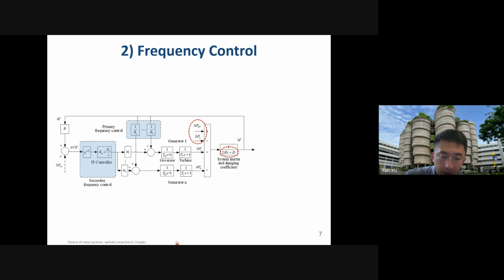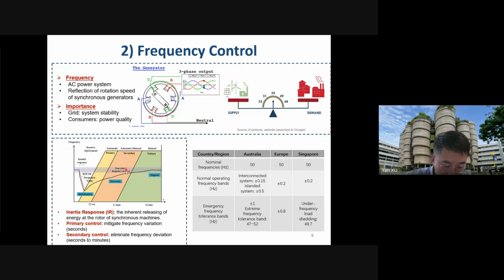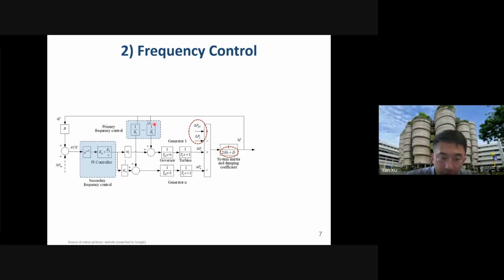Now, as I said, we have two control systems, primary control and secondary control. So you can see, given this delta F, this primary control block will immediately react to this delta F. Here you can see the control unit is 1 over R. R is the so-called regulation coefficient, or droop coefficient. Given this delta F and this R, each generator will have such a primary controller. Then it will generate a signal. This signal will change the position of the governor, and then it will allow more or less gas input, or energy input, so as to restore the frequency a bit. So that is the so-called primary frequency control block. This is denoted in these blocks.